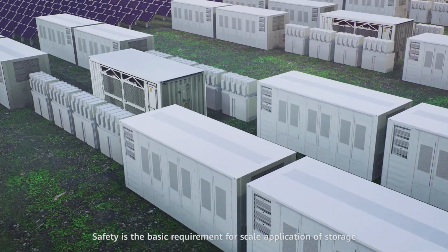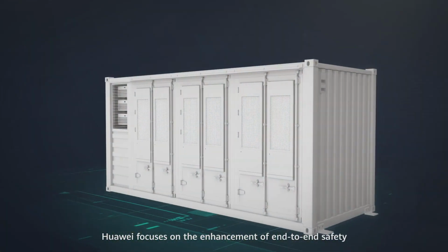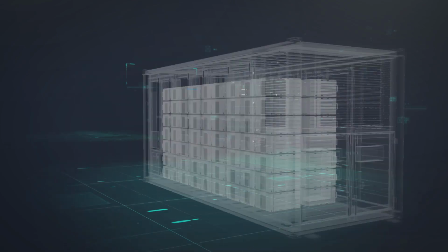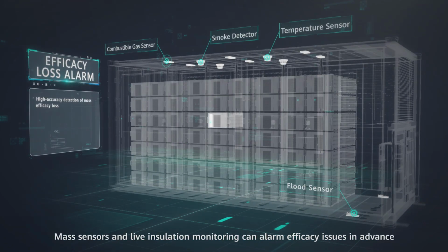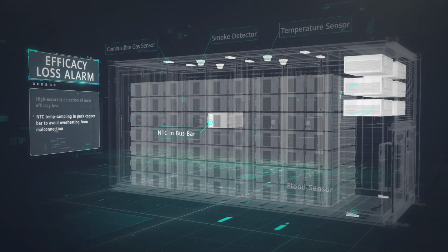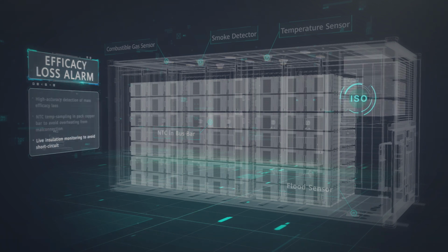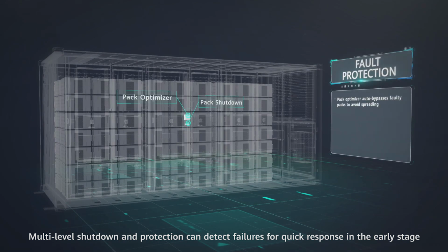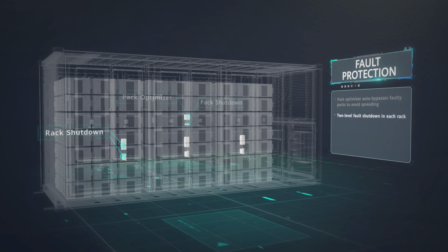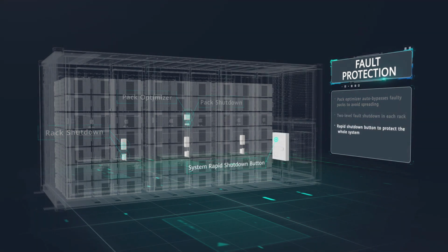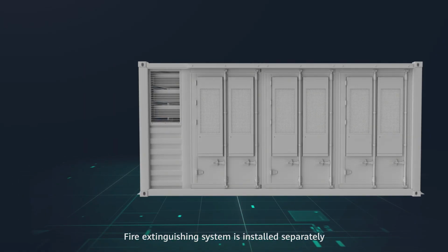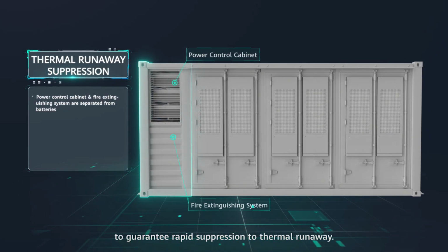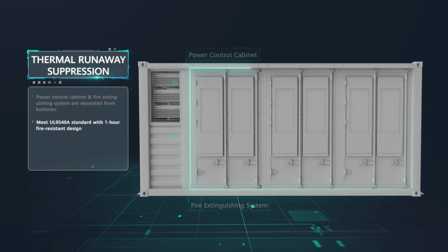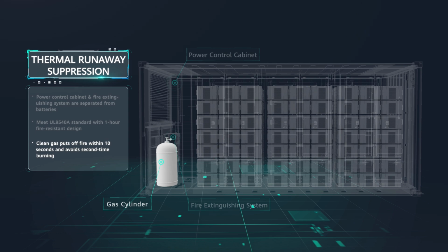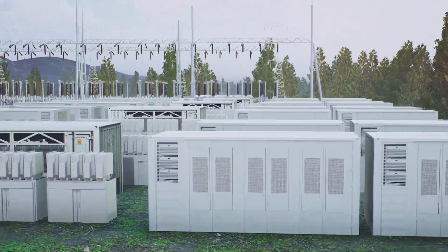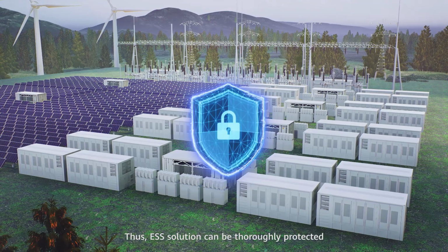Safety is the basic requirement for scale application of storage. Huawei focuses on the enhancement of end-to-end safety. Mass sensors and live insulation monitoring can alarm efficacy issues in advance. Multi-level shutdown and protection can detect failures for quick response in the early stage. Fire extinguishing system is installed separately to guarantee rapid suppression to thermal runaway. Thus, ESS solution can be thoroughly protected.